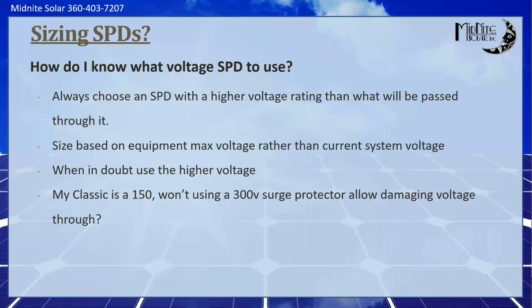And then 6 months later, 2 years later, whatever, the homeowner calls us and says, I'd like to expand that system, or they call a different installer. And they look at that system like, hey, great, we got a Classic 250, we're only running 100 volts VOC. I'm just going to throw one more module in every string and increase the PV array, and I don't have to touch anything because everything else is sized correctly. And then that SPD is going to be bleeding all the time, and you're going to be losing PV production, and eventually the SPD is going to short out and clamp, and you're not going to have any PV production. So that's something to keep in mind.